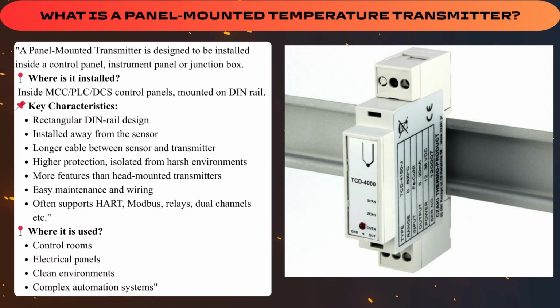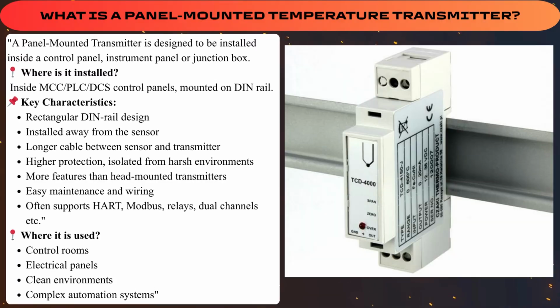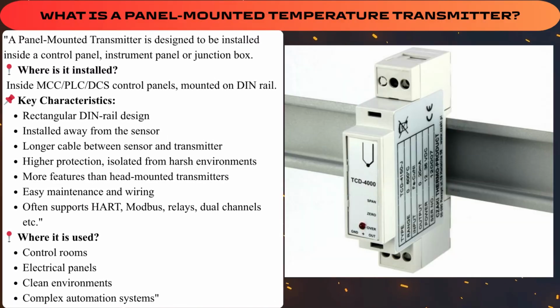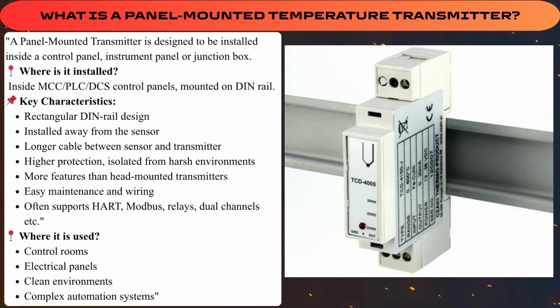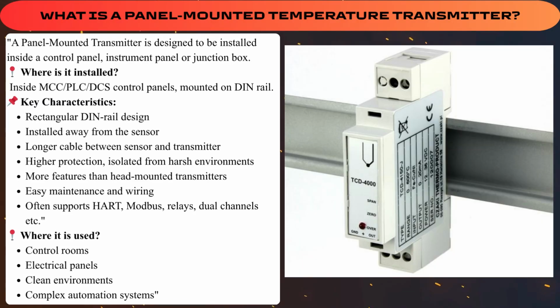What is a panel-mounted temperature transmitter? A panel-mounted transmitter is designed to be installed inside a control panel, instrument panel or junction box. Where is it installed? Inside MCC, PLC, DCS control panels, mounted on DIN rail. Key characteristics: rectangular DIN rail design. Installed away from the sensor.